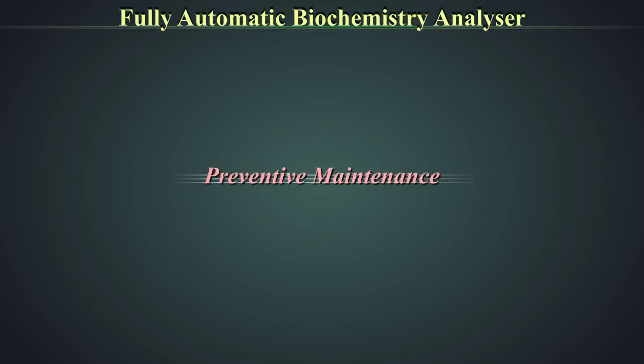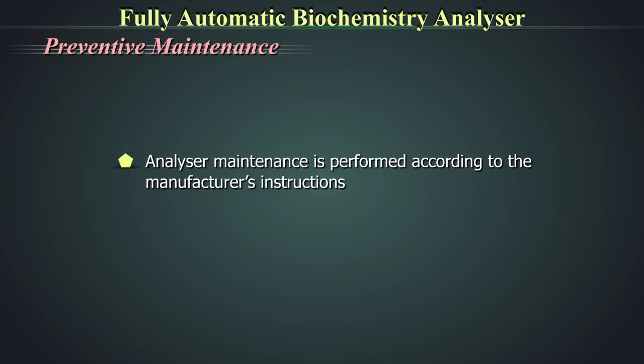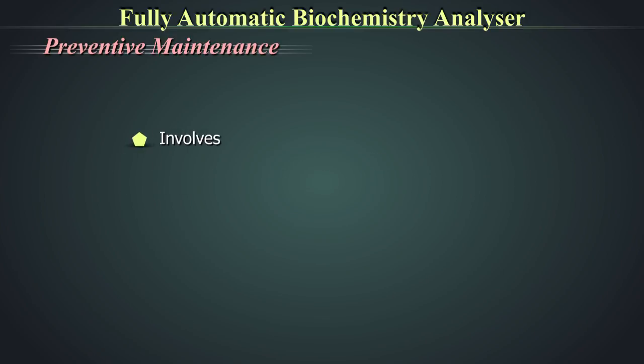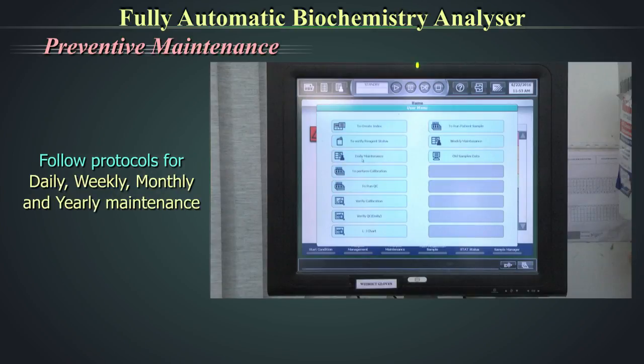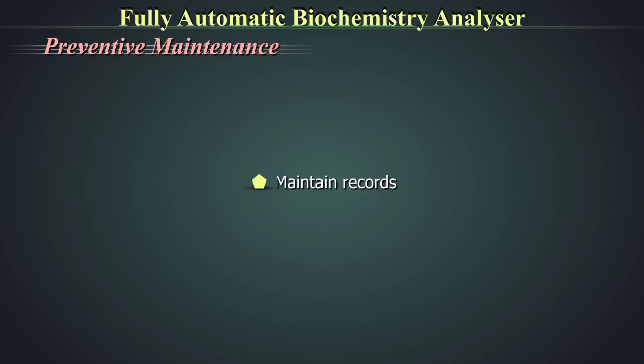Preventive maintenance: Analyzer maintenance is performed according to the manufacturer's instructions. Usually the machine gives reminders of the maintenance schedule. Maintenance involves regular check of the aspiration system, optical system, and measurement system, as well as replacement of parts undergoing wear and tear. Protocols for daily, weekly, monthly, and yearly maintenance should be followed per manufacturer's guidelines, and records of all maintenance carried out should be kept.